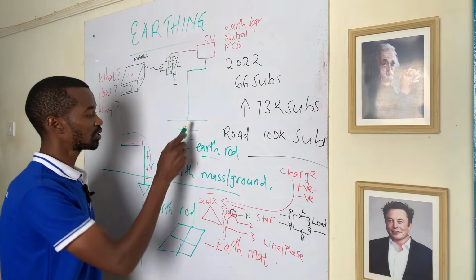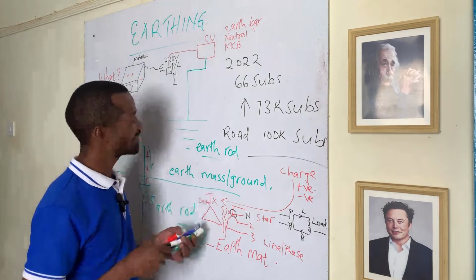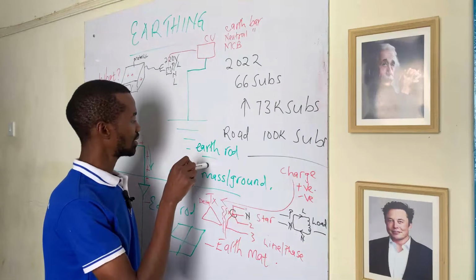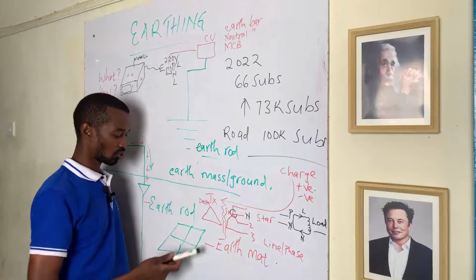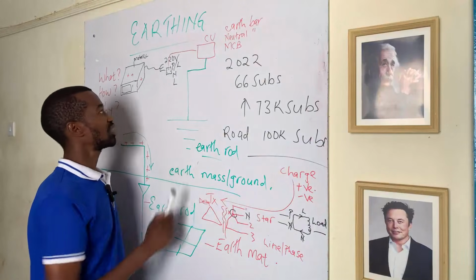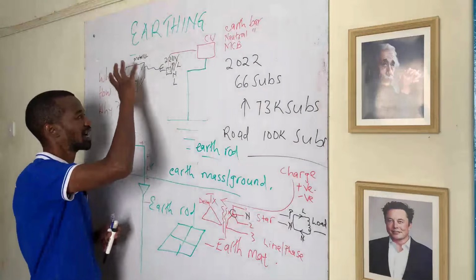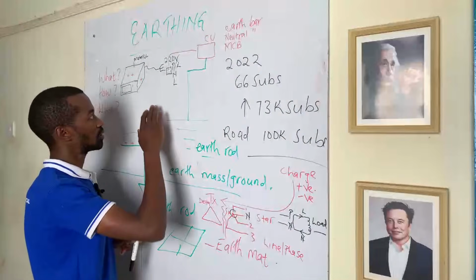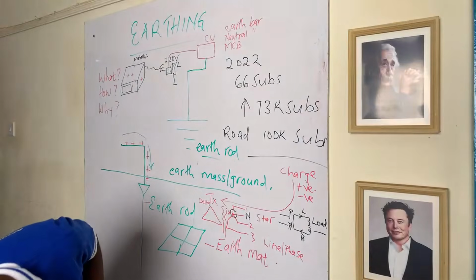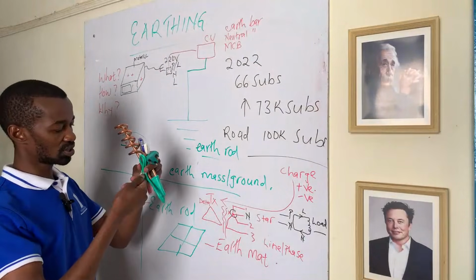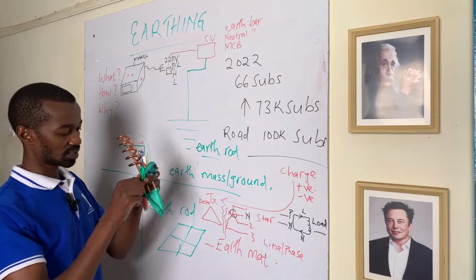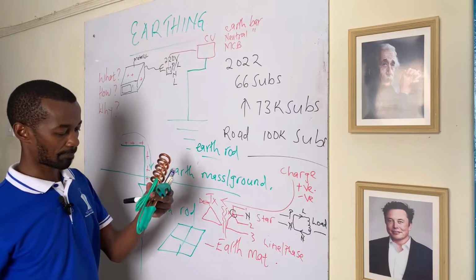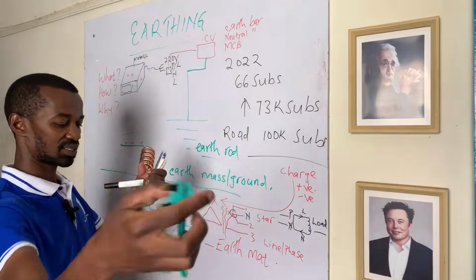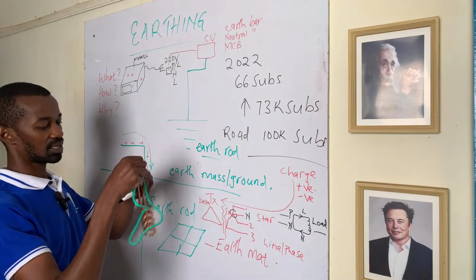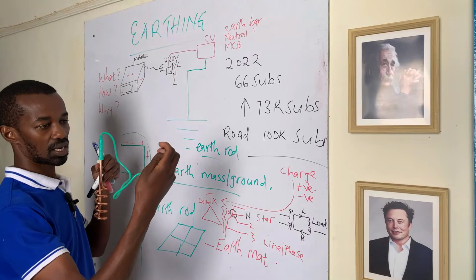So moving on, at this point, we have the earth rod, and it does not end there. If you have this earth rod, it has to be working. Whether it is an earth rod or an earth mat, it has to be working perfectly. So that in case our microwave here or the customer's microwave has any charges, it will go all the way to the top plug, the socket, right? So even if this is the item that the customer is using in the house, there has to be that continuity, my top boss. It will go all the way from this pin right here, like we have discussed, to the wall socket.